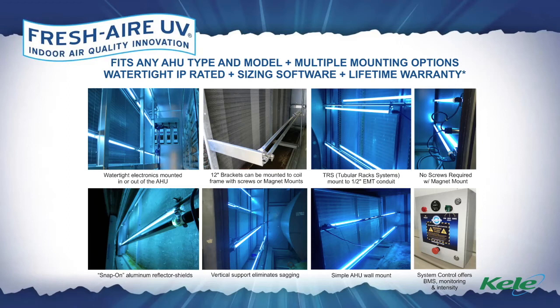We have BMS options and control box options as well. The last picture you see there is an example of our control box option. We oftentimes, for this level of control, use a sensor, a UV sensor called the radiometer. We would use this for, let's say, a bioterrorism application where they want to guarantee a certain level of UV dosage or UV irradiance intensity to make sure that the units are running as they should in order to address biological contaminants that may be passing through the system.